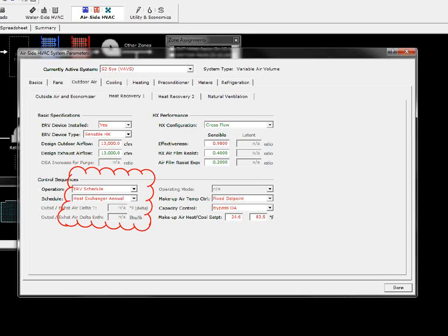So that's the only time these runaround loops are utilized. I figured I could model it, it's not a wheel, that wouldn't be a very good application, so I modeled it as a plate and frame heat exchanger. And again, they're not running all the time. I would like to take credit for that 13,000 CFM and put 13,000 CFM in my LEED baseline model all the time, but I would have killed it. Between me and the design engineer in our office, we figured that these purge systems would be used once a week during school non-break times. So I came up with this annual heat exchanger schedule, and it basically operates the ERUs one hour a week during school sessions.